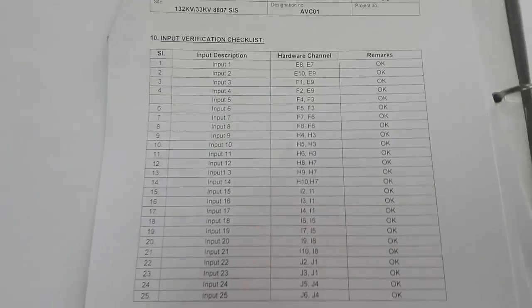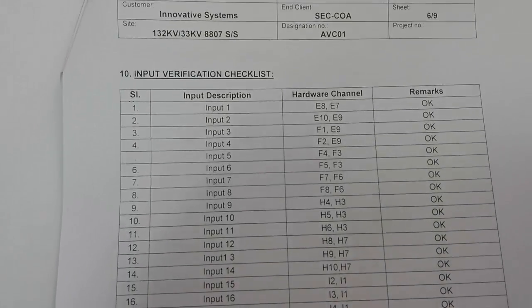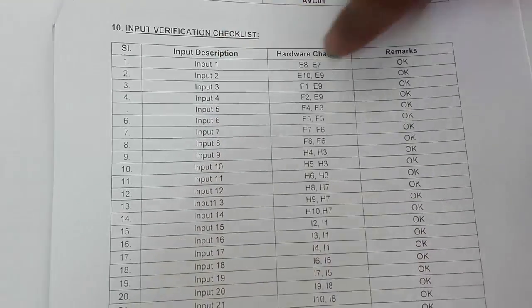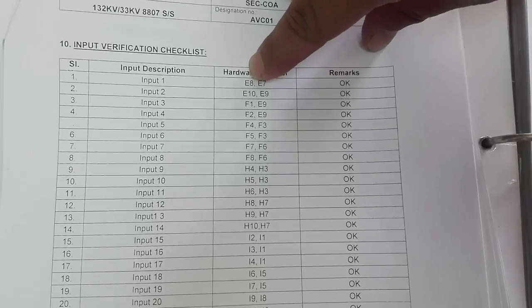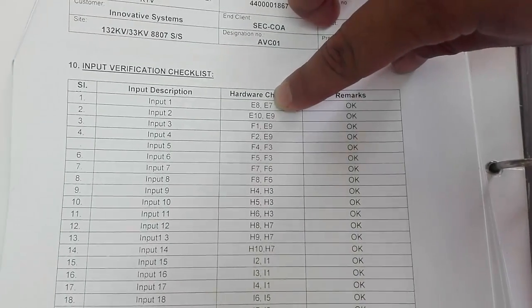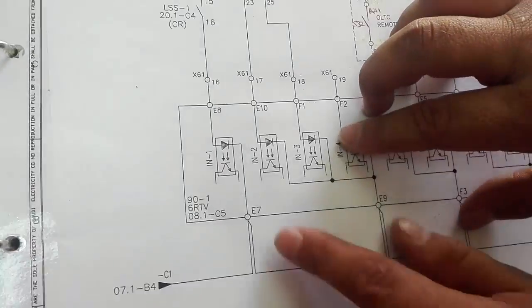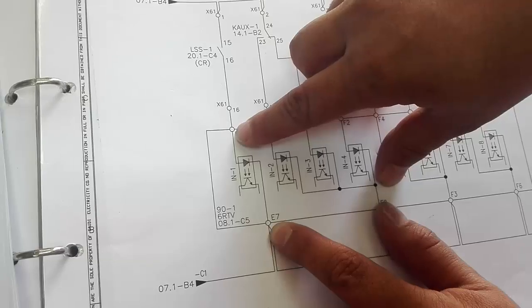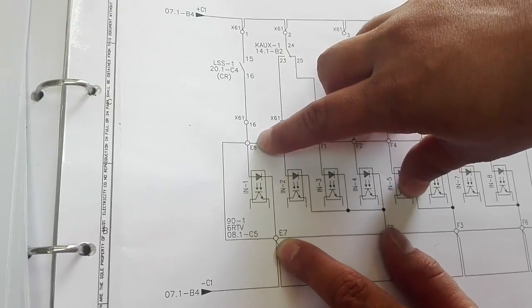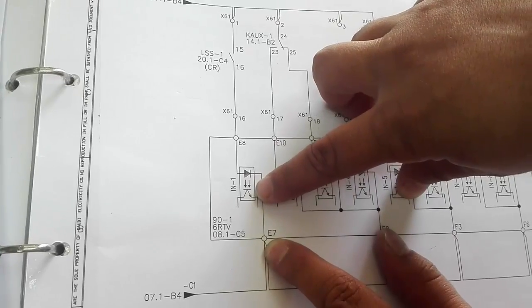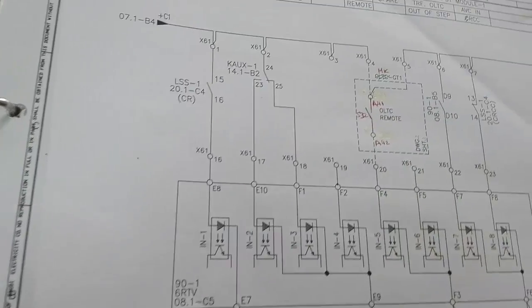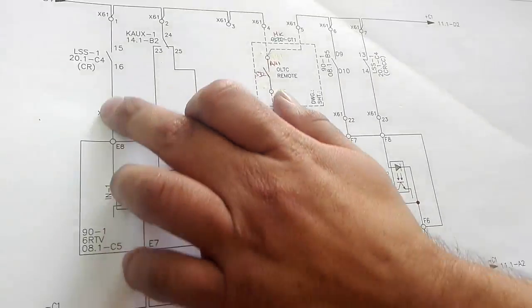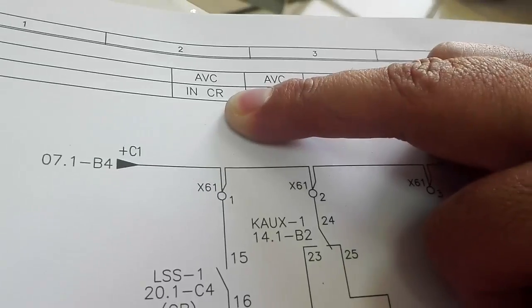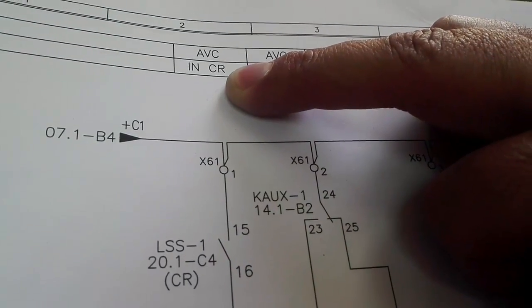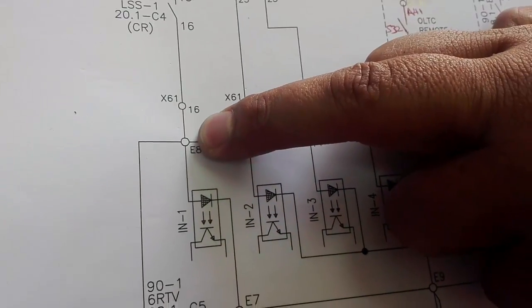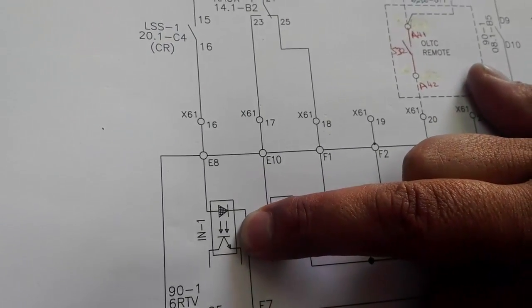Now we will show the digital inputs. Okay, so from the table you can see input 1 belongs to which points, E8 and E7 of our ZIV relay. Now show it in the drawing. E7 negative, E8 positive. So when it gets positive at E8, it will change the status. Similarly, when AVC is in CR, it will get energized. And E8 will get energized and our input 1 will change the status.